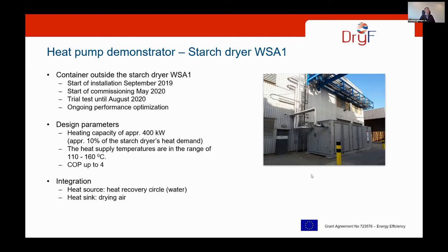The design parameters of this heat pump were a heating capacity of 400 kilowatts, which is approximately 10% of the overall starch dryer heat demand. And we were expecting to have 110 to 160 degrees Celsius as heat supply temperature, with a COP of up to 4. I will later show you some results, and I will tell you a little bit more about the integration a few slides later.